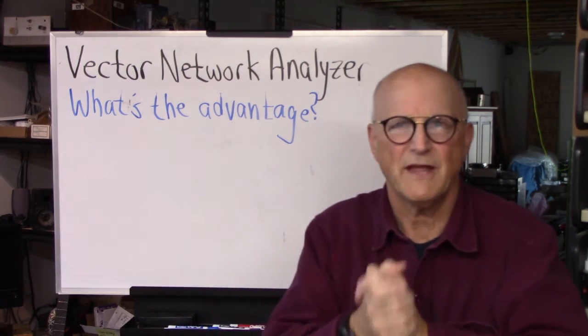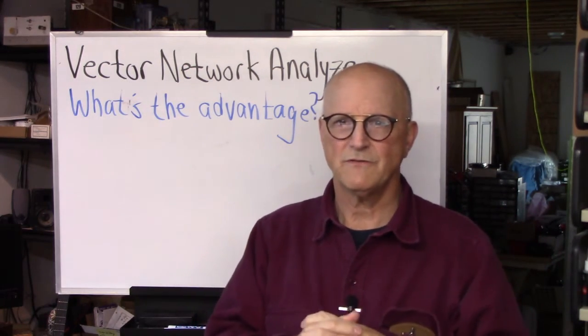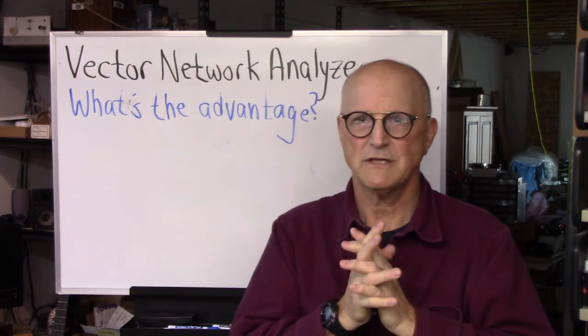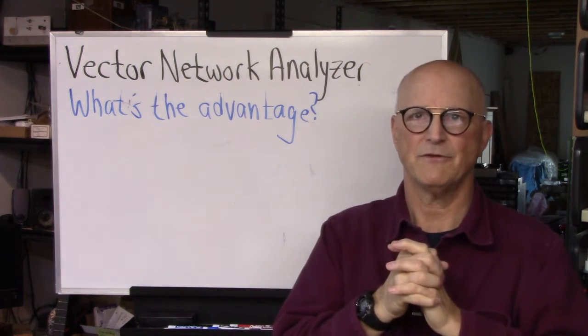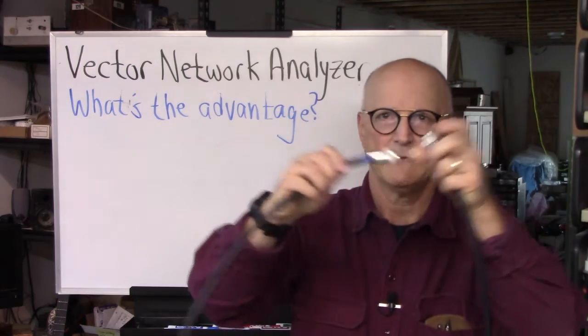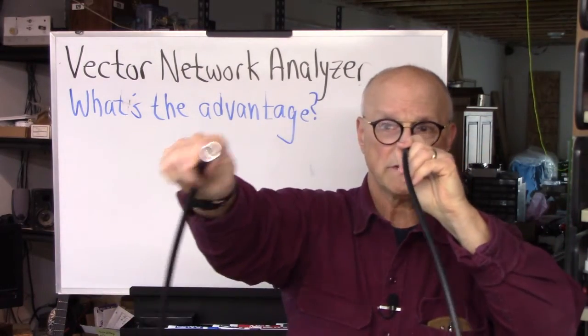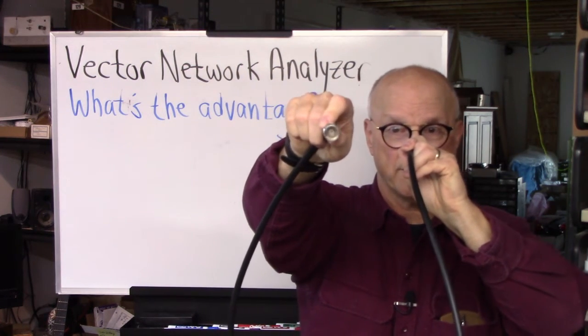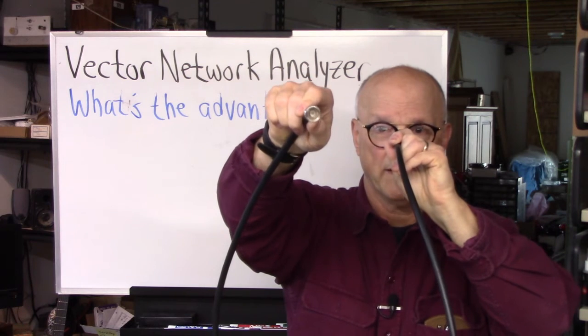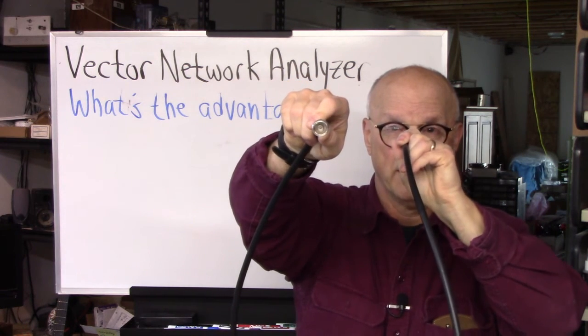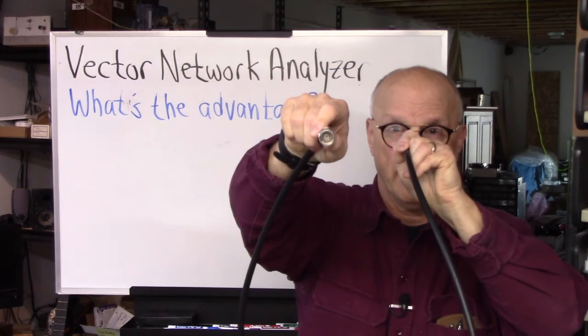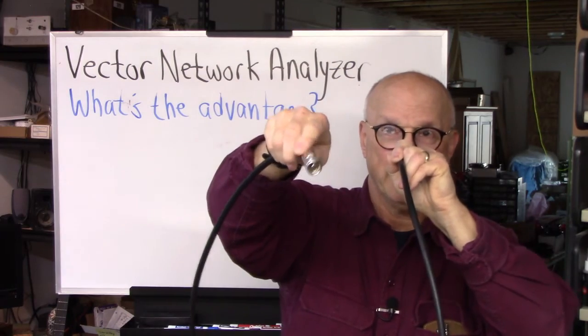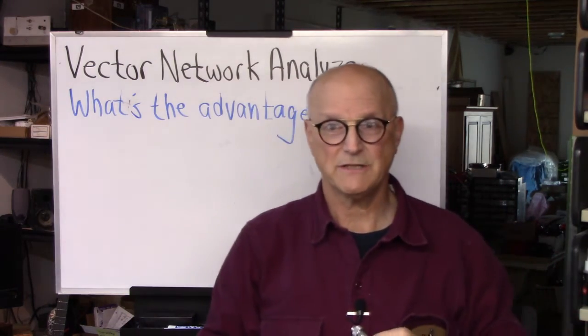So how does it do that? Well when you're going to use the VNA for measuring something, you go through a calibration procedure using the interconnecting cables. The VNA then takes your interconnecting cables and looks out through the interconnecting cable at the calibration standards. Now it makes certain assumptions about the calibration standards you're using. But it's looking out there and it sees the effects of the cable on what it expects to be at the end where you have your calibration standard.